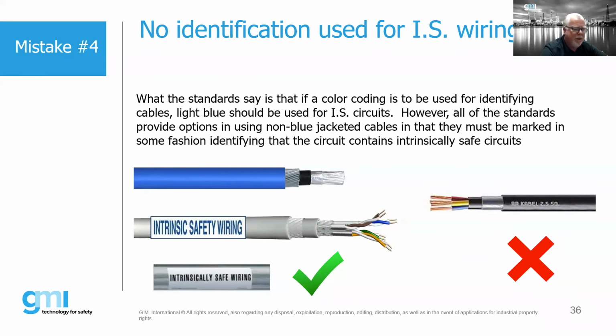So light blue is absolutely a good means to identify our intrinsically safe circuits. However, I know there are people out there saying, I need to find light blue cable for my intrinsically safe circuits. If you read the standards very closely, the standard doesn't say that it must be light blue unless you're using a color to identify your IS circuits. Exactly. What you can do, and this is commonly done, is put cable tags, markers, or some sort of identification on other colored cables saying this is intrinsically safe wiring. What we don't want is a cable that is carrying intrinsically safe circuits but is not labeled. So we do need to label it.